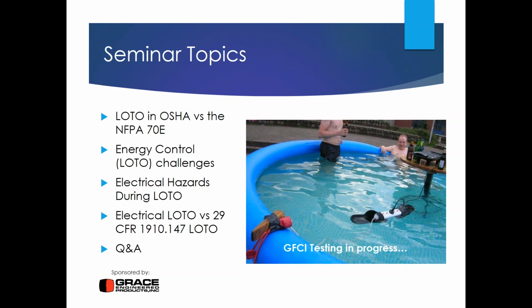We're going to talk about some of the energy control and lockout tagout challenges that exist. Some of those challenges are in the form of the configuration of the equipment or the type of equipment. Some equipment is not lockable by its design, due to its age or because it comes from a foreign country. We'll talk about some of the challenges you might face, and in particular some axioms that you can use to protect yourself in those situations where the standard issue lockout tagout wouldn't apply.